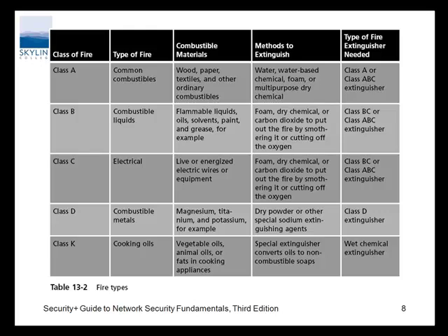Class D is magnesium and combustible metals, and they say dry powder or special sodium extinguishing agents. Sand also works pretty well on these. If you put water on this, you're going to have a problem. Sand generally is going to work pretty well on those things.